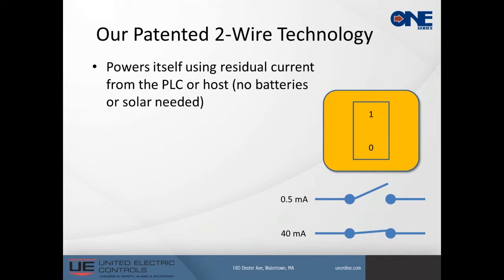The way that this technology works has not changed much at this point from the old technology of the 1 Series. And just to review it, it's fairly simple. It powers itself using residual current from the PLC or the host, no matter what that host is. It could be a solenoid valve, it could be an interposing relay. There's always that leakage current less than 480 microamps available that we use to power the 1 Series. No batteries, no solar, nothing else needed to get this done.